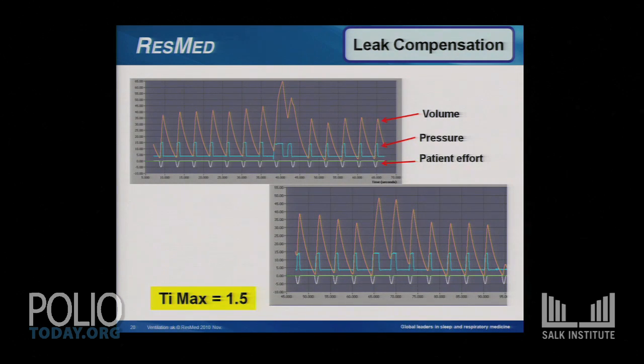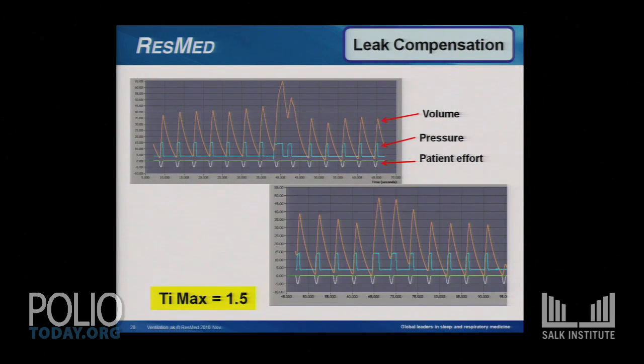Now what we can do to reduce that asynchrony is set that TI maximum. So on this particular patient, exact same situation, we created the big leak right here, but notice the difference between this breath and this big long breath. The difference is we put in those brackets. We put in that TI max right here. And we said, this is the longest breath we'll allow this particular patient to take. That way, when the mask comes loose and they get the big leak, they don't have an abnormally long breath. And look how quickly synchrony was restored because we set this TI max. The very next breath is right in sync. So we only had one breath, just a tiny little bit extra long, and the very next breath was back in synchrony with the patient. So we can use the TI max setting to ensure synchrony in leak conditions.